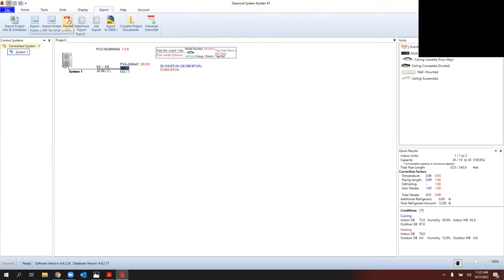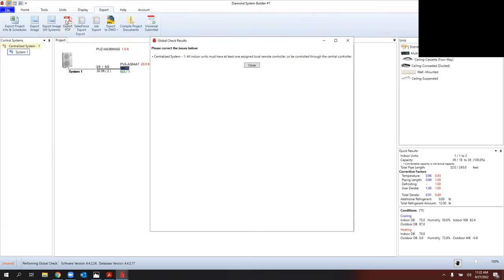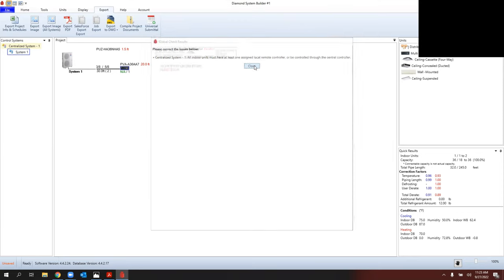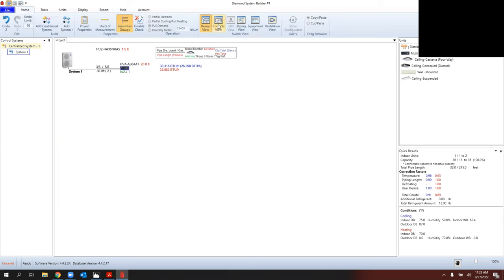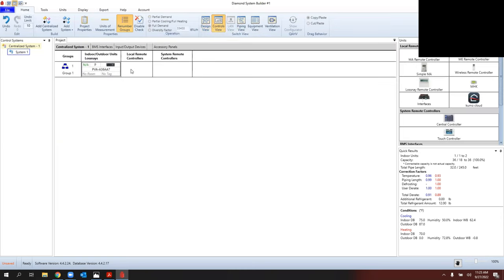The number one call I get is that people try to export quickly. If you select Export as a PDF, it throws an error code — it runs a global check to ensure systems are compatible. In this case, it's reminding me there's no controller with that ducted system. This is one of the best features of Diamond System Builder: it won't let you design an incompatible system. It also gives you outputs like operating conditions, BTUs available, and for multi-zones, how much refrigerant charge to add.